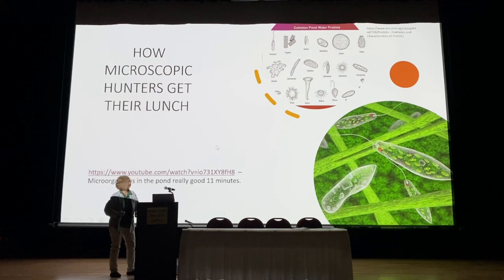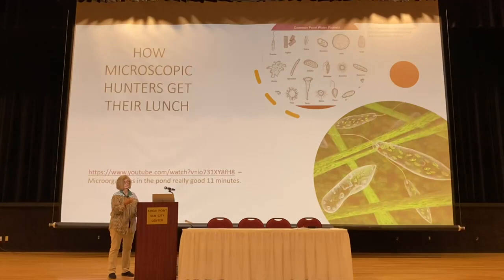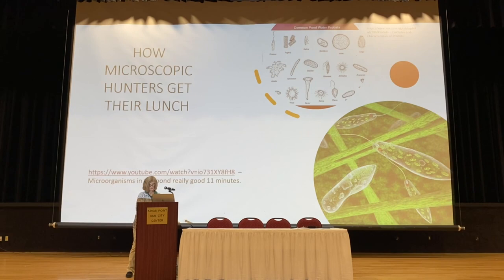My gosh, all of this going on. Every week I would look into the microscope — I worked with domestic waste — I would take just a drop and look at the biomass. They're really indicator organisms for the health of the biomass or the tank. Whatever was predominating, I could tell basically the quality. If it had a lot of rotifers, that means it was pretty well aged and the effluent wouldn't have a lot of organic load going out. If ciliates were dominant, it had a little more organic load but had the oxygen it needed. Did anybody find it interesting, or am I the only nerd here?